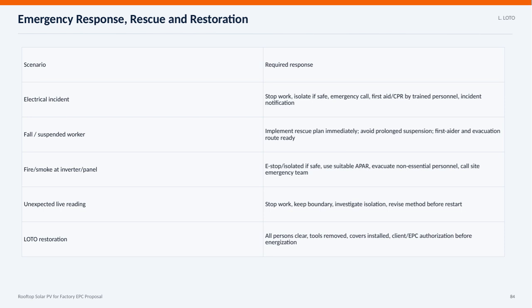For fire or smoke at the inverter or panel, an emergency stop or isolation is necessary if it's safe, followed by using the appropriate fire extinguisher and evacuating non-essential personnel. Any unexpected live readings require stopping work, establishing a safety boundary, investigating how to isolate the issue, and revising the method before restarting operations. Finally, for LOTO restoration, it's crucial to ensure all personnel are clear, tools are removed, covers are reinstalled, and authorization is obtained from the client or EPC before re-energizing the system. These steps are vital for maintaining a safe working environment throughout the project.